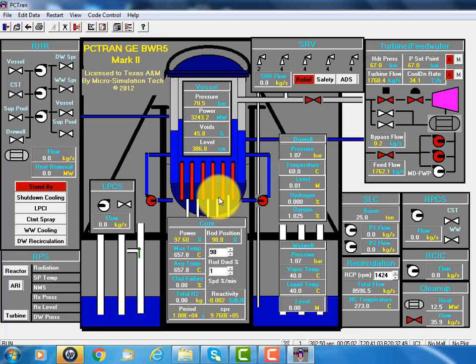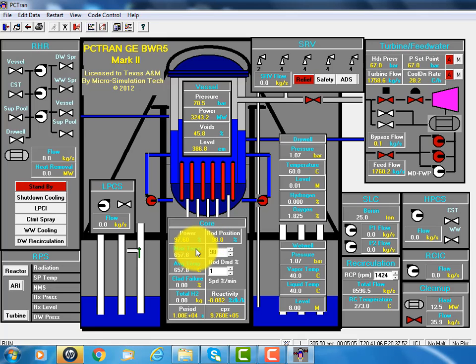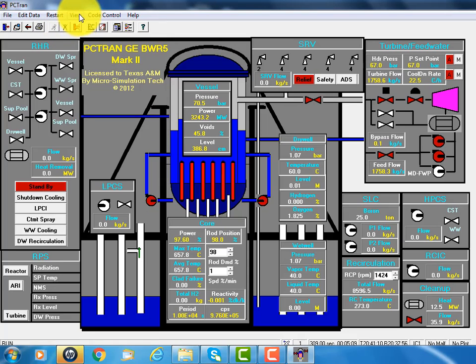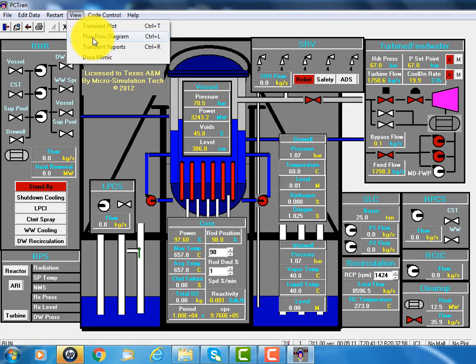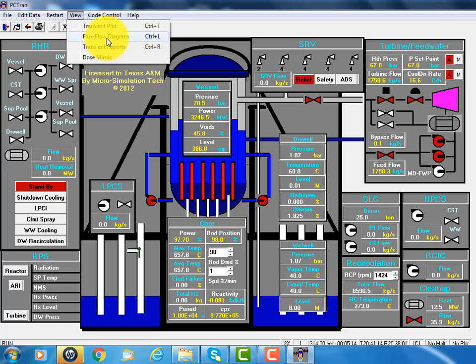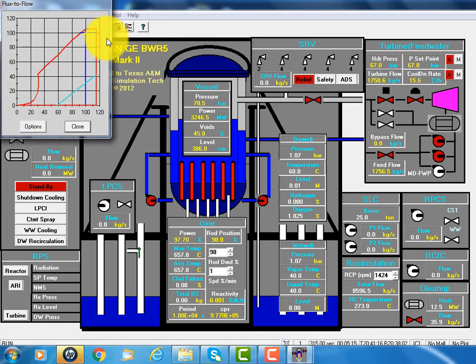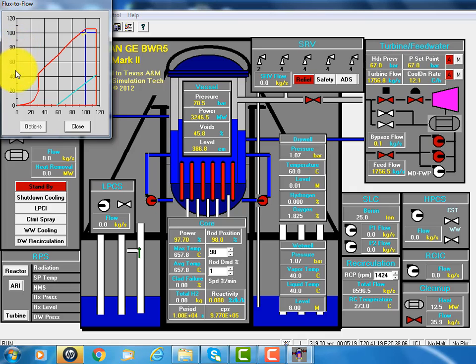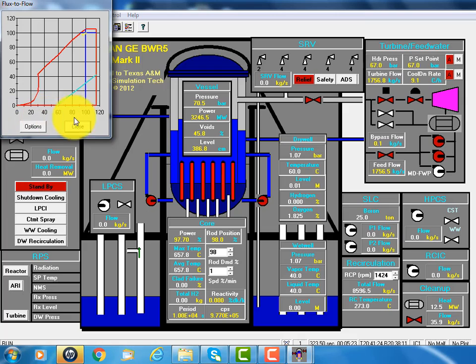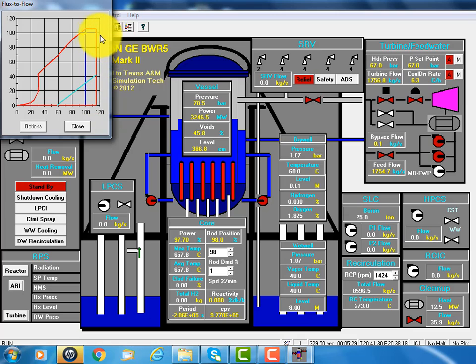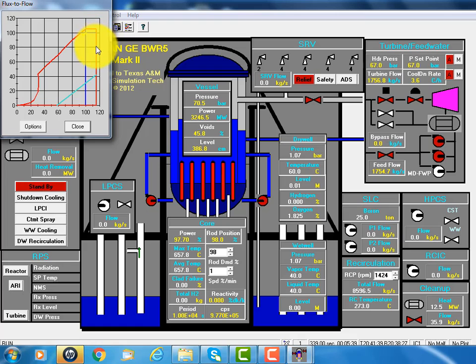You see, original power is 100%, now it's down to 97%. And the operator will go to a chart, and we click the view, and flux flow diagram. Vertical axis is the flux, neutron flux, in percent. Horizontal axis is the core flow, also in percent. You see, originally it's at 100%, both are 100%. After we reduce the recirculation flow, the power goes down. So the yellow operating point moves to the lower left.